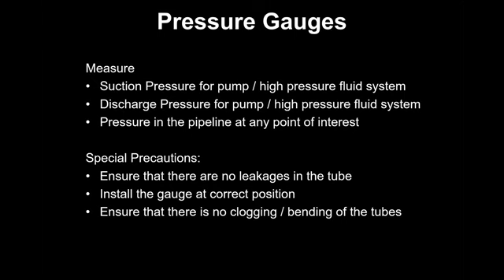So what we do is we do the pressure measurement to see the profiling of the pressure from the primary pump, secondary pump, then to the first AHU, third set of AHUs, to see if the pressure values are appropriate. We can also calculate the pressure drop in the individual equipment to see whether it is as per the design values or not. So pressure gauges are used extensively.